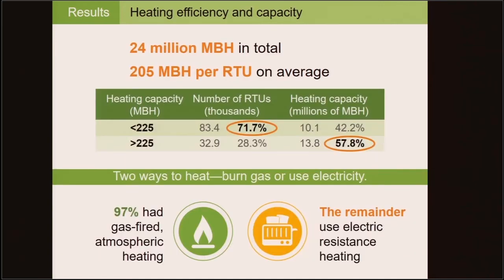The total estimated heating capacity of RTUs in Minnesota is approximately 24 million MBH, with an average heating capacity of 205 MBH per RTU. Nearly 3/4 of individual RTUs have a heating capacity less than 225 MBH. However, RTUs with heating capacities over 225 MBH comprise 58% of the heating capacity of all RTUs.